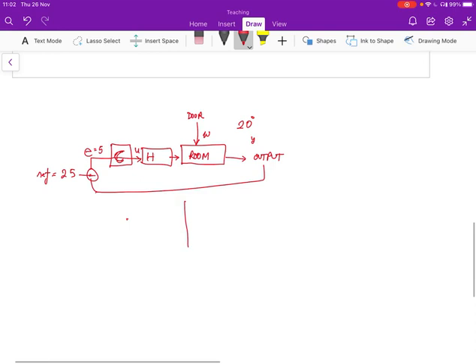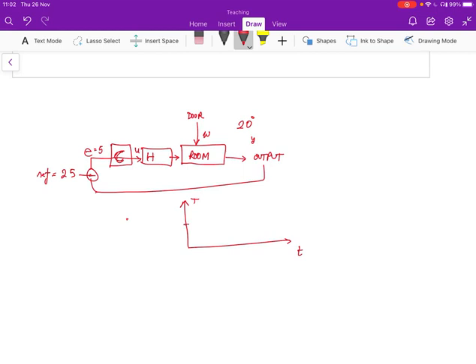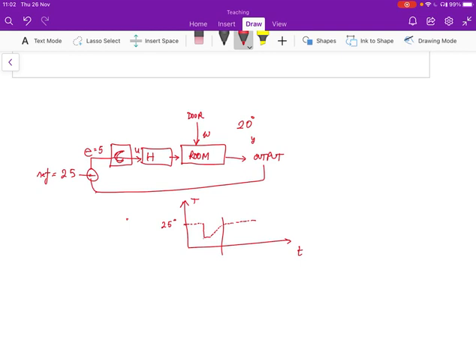So if you were to look at the time and the temperature value, we'd like to see something like this. So this is 25 degrees, which is our reference. And let's say we were at 25 and the door opened, that would be a sharp transition down. And then the controller is going to respond after a while. It's going to kick in and hopefully it recovers like so. And so this is the time from here to here is sort of the response time.